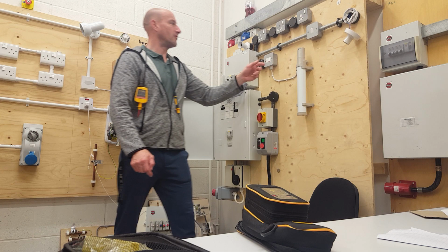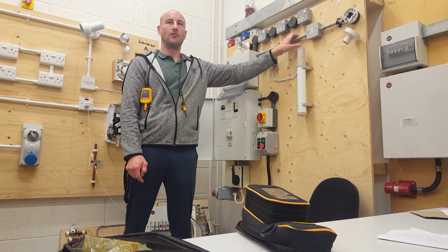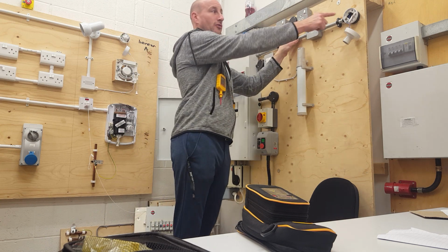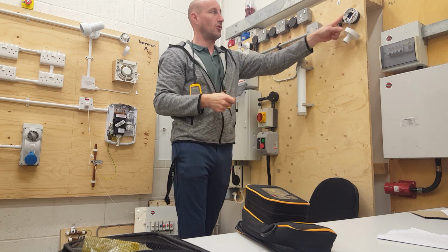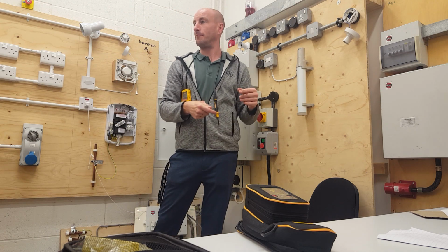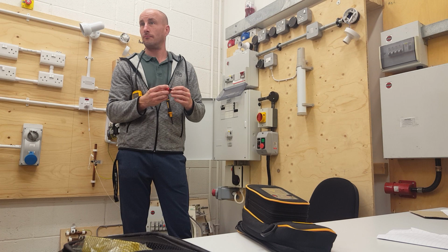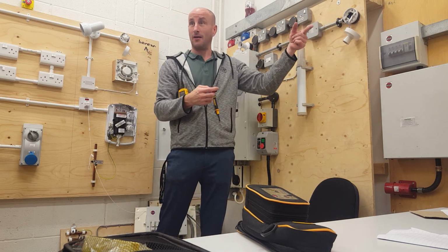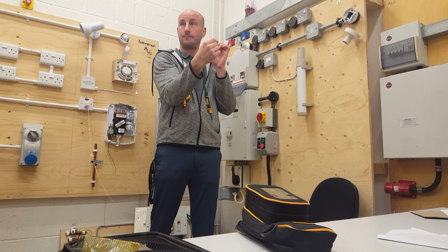So far what we've seen in the workshop, when anything's in conduit, there's never a neutral at the switch, because the neutral comes from here and just goes straight through to the light. So we can't test here because there's no neutral to test, so it's got to be at the light. How many tests do we do at the light? Three, yeah. Is there anything else we need to do? How's there no neutral in the switch? Because it just goes straight through. There's a wire there, but there's no connection, it's just the wire.